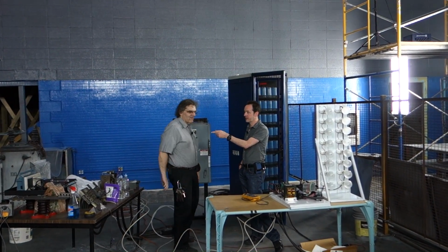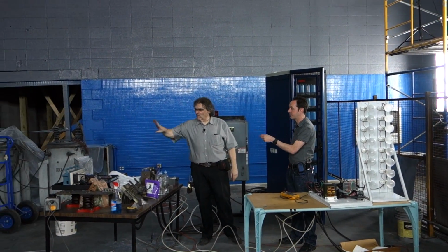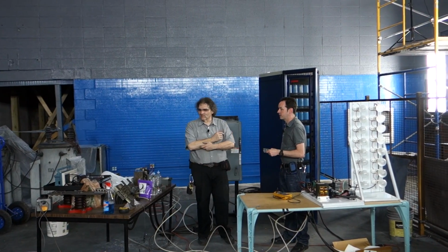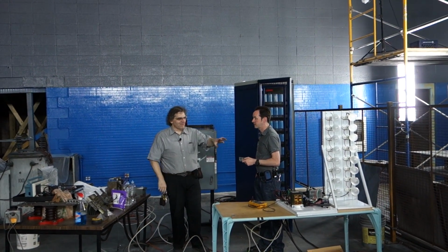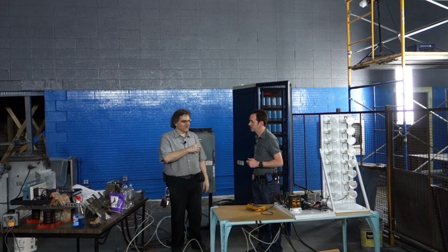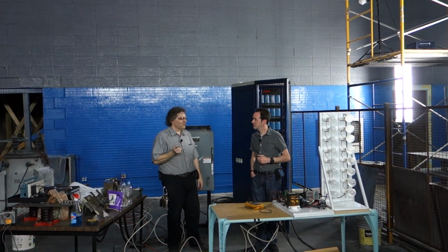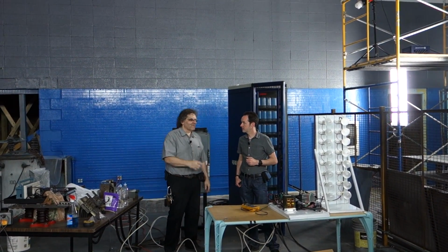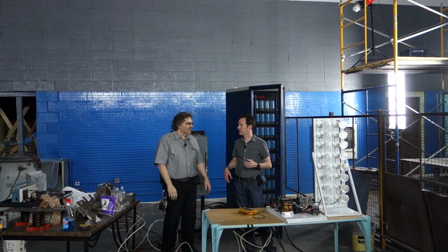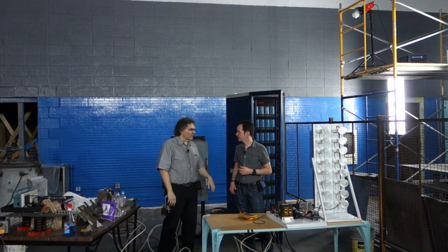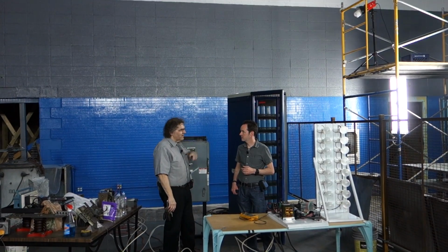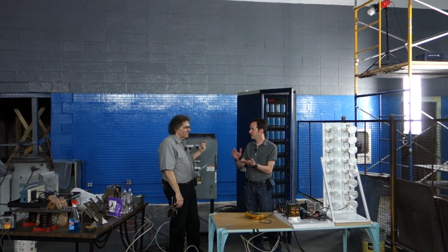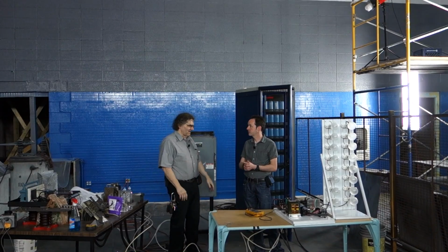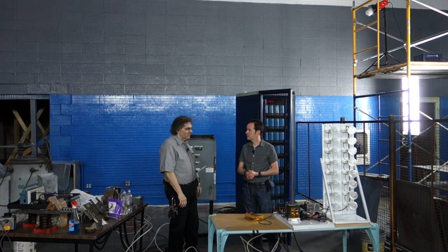Now I see we got the DSO up here and stuff like that. Well, we were actually using the DSO. The downstream from the rectifier is rectified AC, so you can't put a DC meter on rectified AC to get a reading - that's why the meter reads wonky right now. Normally the meter is reading directly across the capacitor bank, and that's exactly like a giant filter. So that's not in the circuit, so the meter doesn't work.